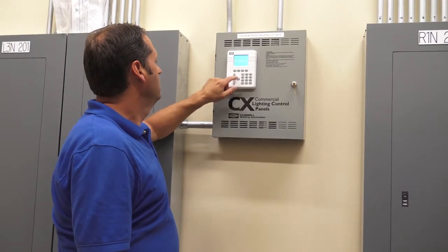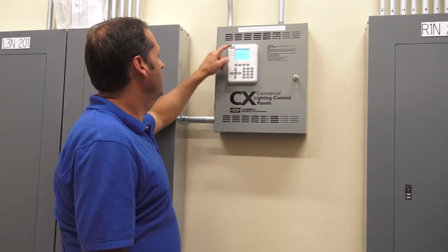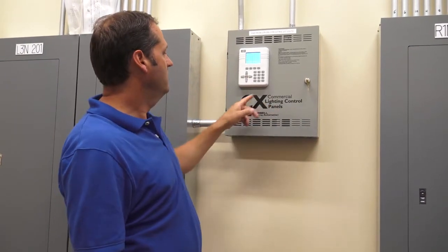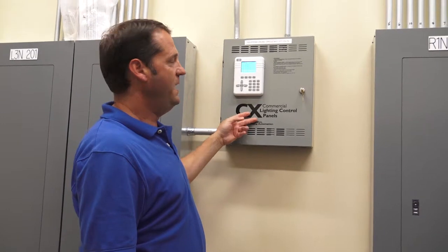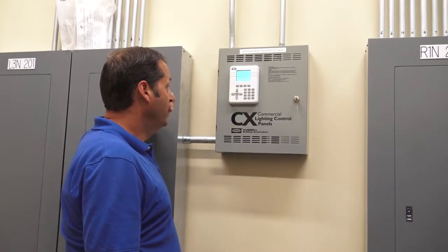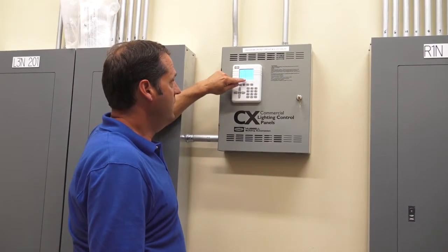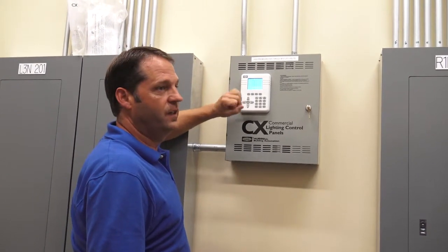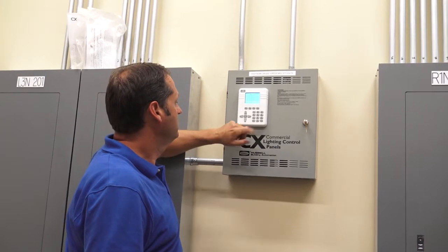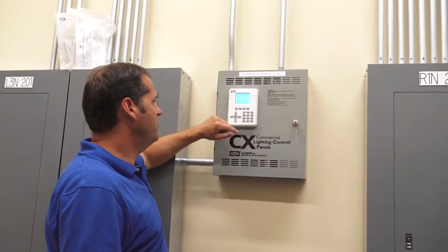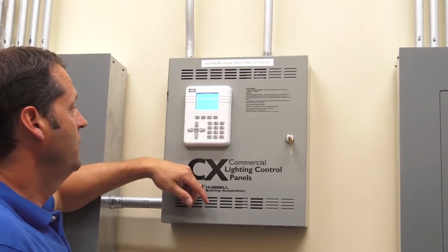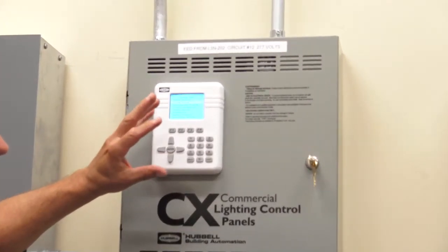There's your outputs, your inputs. There's nothing right now. I don't remember which input that switch is landed on, but if they were operating that switch over there, and it was on input number 7, you'd see that little circle fill in to dark. So again, troubleshooting or diagnostic type functions are in system status.